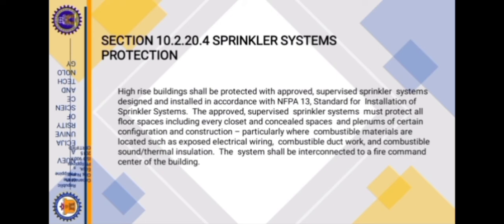Sprinkler Systems Protection. High-rise buildings shall be protected with approved supervised sprinkler systems designed and installed in accordance with NFPA 13 standard for installation of sprinkler systems. The approved supervised sprinkler systems must protect all floor spaces, including every closet and concealed spaces and plenums of certain configuration and construction, particularly where combustible materials are located, such as exposed electrical wiring, combustible ductwork, and combustible sound thermal insulation. The system shall be interconnected to a fire command center of the building.